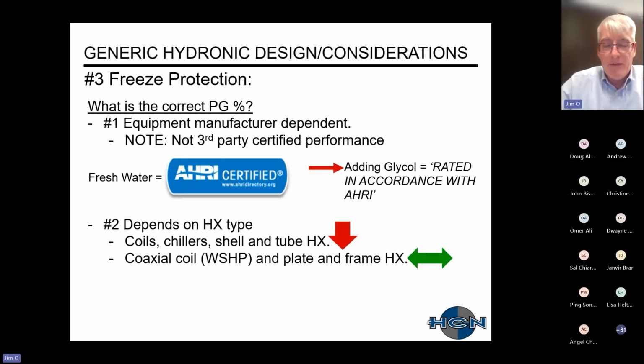Just want to point out that the percentage does greatly depend on the type of what I'll call heat exchanger that you're using. What I found is that for coils, chillers often have shell and tube heat exchangers. There's usually a pretty significant derate. But when you have a water source heat pump that has a coaxial coil, or plate and frame heat exchanger, there's not really too bad of a derate.